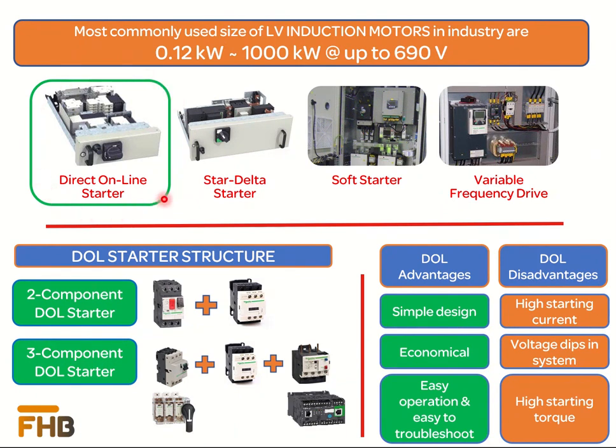Direct online starting is the simplest and most economical starting method used for starting the induction motor. Due to the simplicity of design, it is easy to operate, and in case of any fault, it is easy to troubleshoot. However, it is important to note that with this starting technique, the starting current of the motor can be as high as 7 times the motor nominal current. Therefore, the power system should be able to handle that amount of starting current.